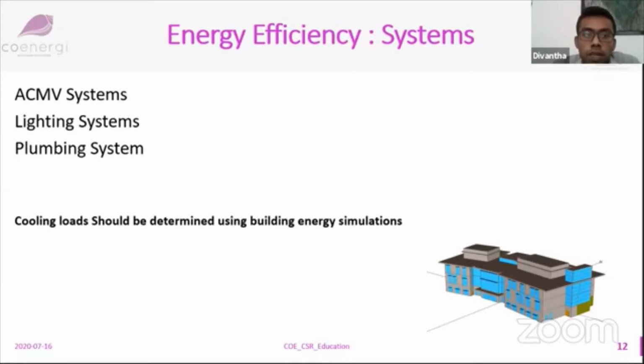And as you already know, the thermal heat gain into a building, into a space, can depend on many factors including climate, orientation, glazing ratio, and thermal properties of the envelope. So the cooling load per square foot or square meter is not always the same, it is not a general thing. So if you use the rule of thumb value to determine your cooling load, you will most likely end up with an incorrect value, and it will most likely result in oversizing or undersizing your air conditioning system. So that can ultimately result in operational issues as well as thermal comfort issues. So this will always negatively affect and increase your operational cost.